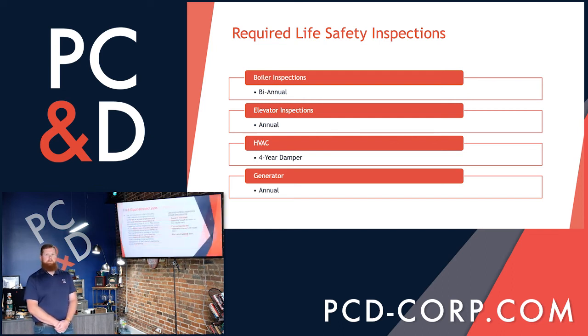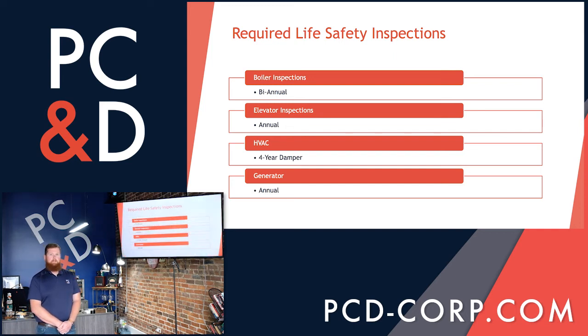Following that, your elevator inspections, typically done by your local municipality, will take place annually. They need to have their certificates posted inside the cab itself, as well as a copy inside your life safety binder. Every 4 years, your HVAC system will need to have its dampers inspected. Typically, you would find your dampers a part of your HVAC system if they break through a firewall or if the system is in excess of 5 tons.